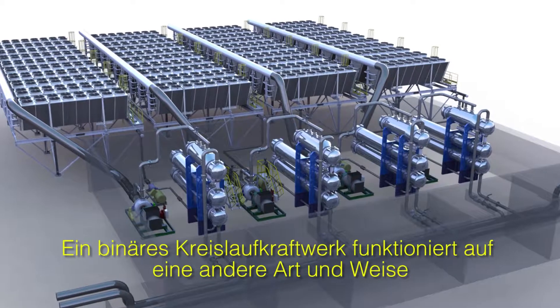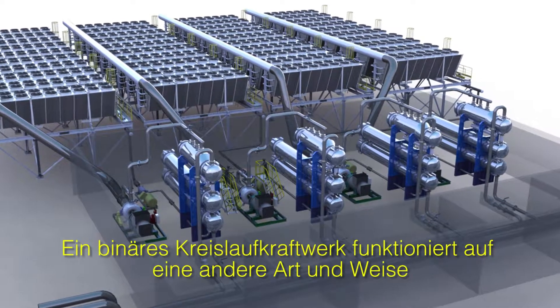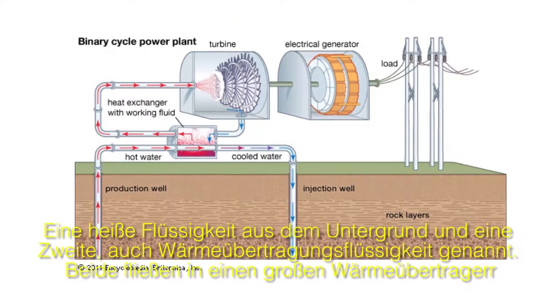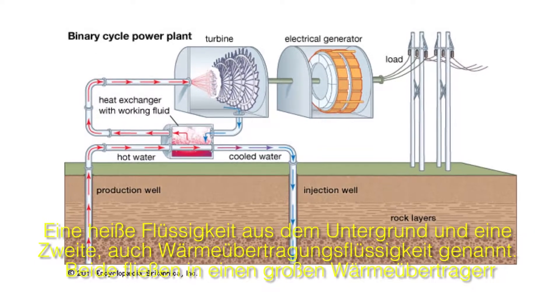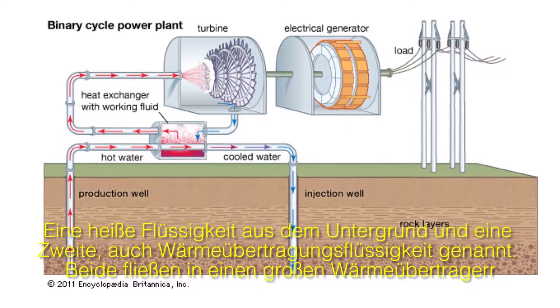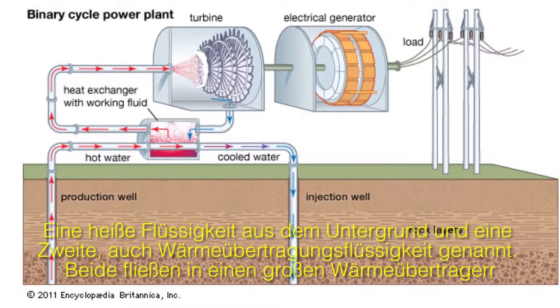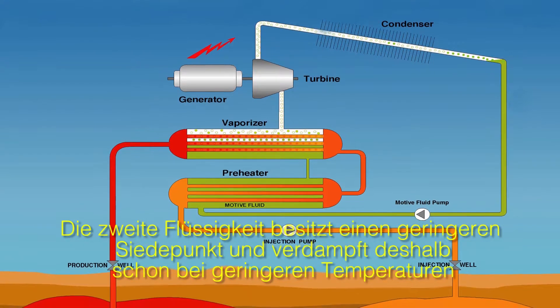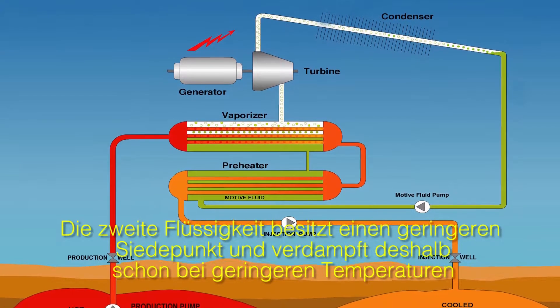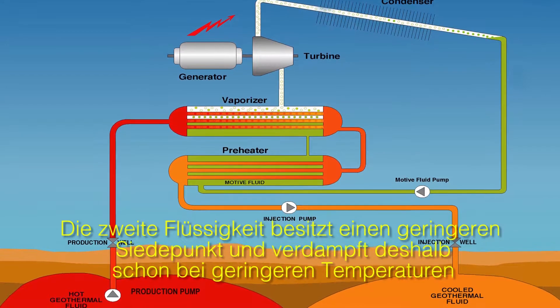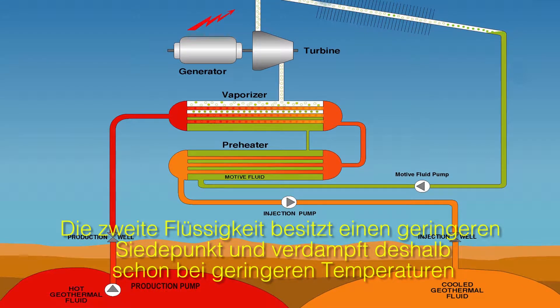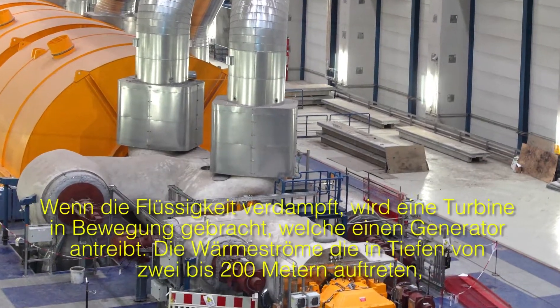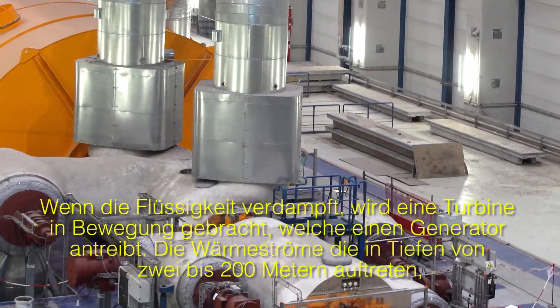A binary plant works differently — it uses two types of fluid. Hot fluid from underground heats a second fluid, called a heat transfer fluid, in a giant heat exchanger. The second fluid has a much lower boiling point than the first fluid, and so it flashes into steam at a lower temperature. When the second fluid flashes, it spins a turbine that drives a generator.